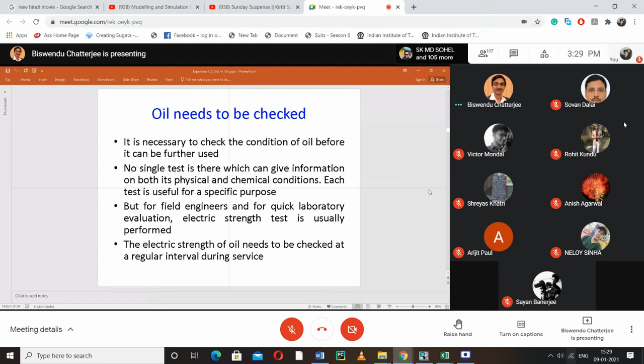Now the electric strength of oil needs to be checked at a regular interval during service to ensure that the insulation is okay. On use, the breakdown voltage will gradually fall. First, let us go to the standard of IS 335, which determines several properties of oil. I think in your material class you have read this in detail. I will just have a recapitulation before we start our experiment.